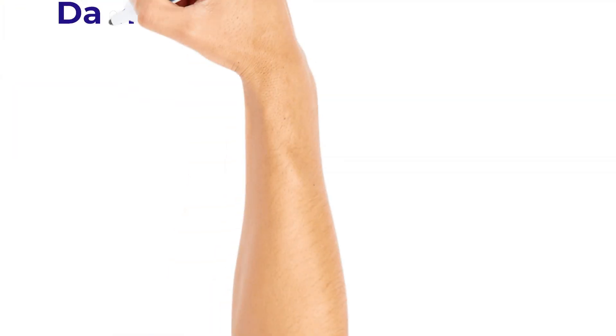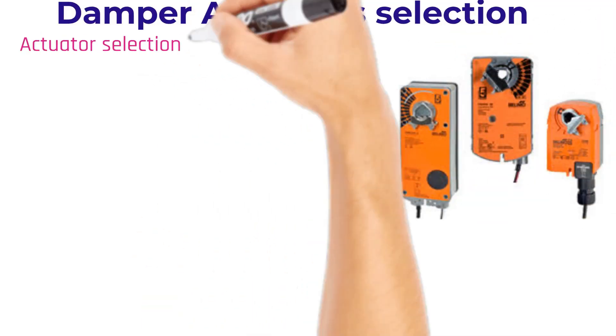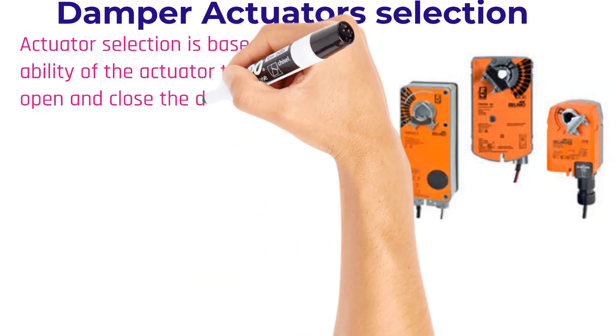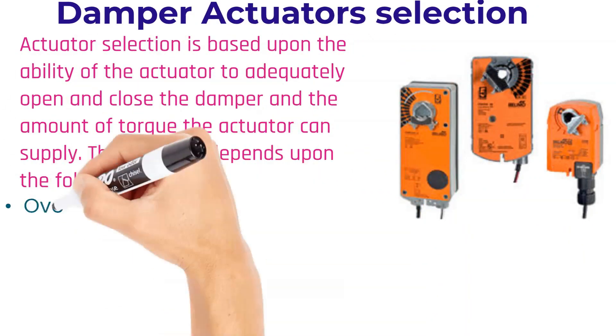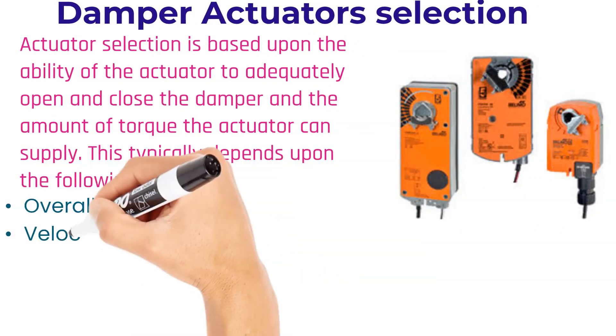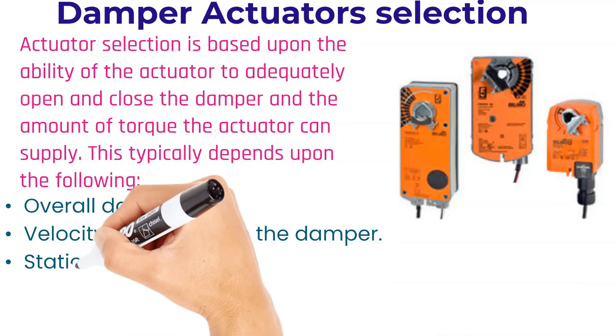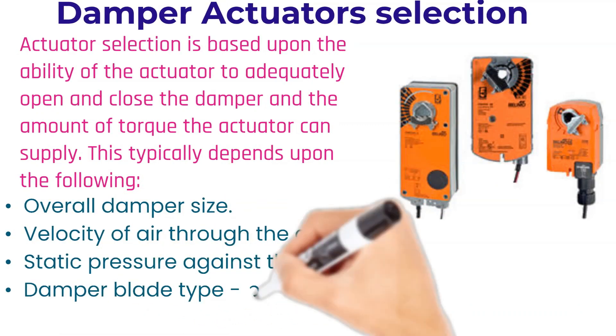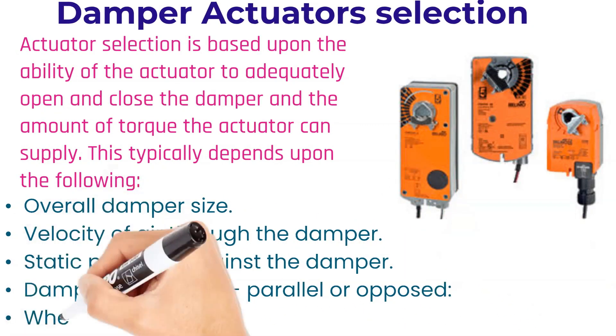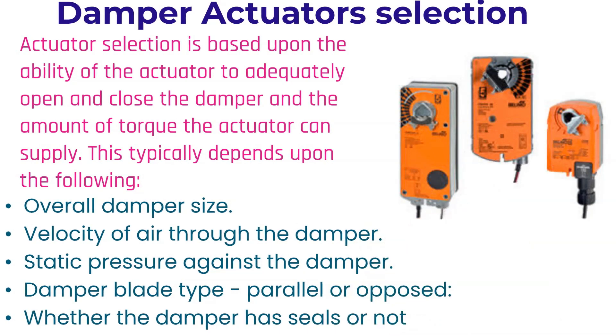Actuator selection is based upon the ability of the actuator to adequately open and close the damper and the amount of torque the actuator can supply. This typically depends upon the following: overall damper size, velocity of air through the damper, static pressure against the damper, damper blade type — whether parallel or opposed — and whether the damper has seals or not.